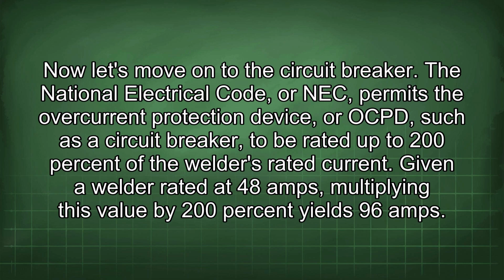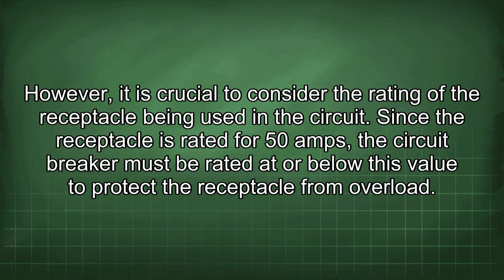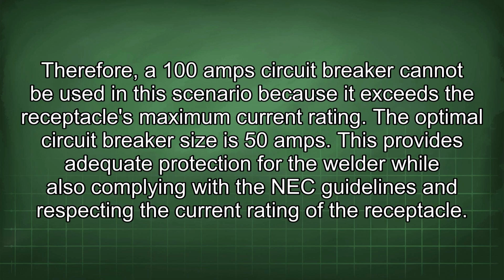The National Electrical Code, or NEC, permits the overcurrent protection device, or OCPD, such as a circuit breaker, to be rated up to 200% of the welder's rated current. Given a welder rated at 48 amps, multiplying this value by 200% yields 96 amps. However, it is crucial to consider the rating of the receptacle being used in the circuit. Since the receptacle is rated for 50 amps, the circuit breaker must be rated at or below this value to protect the receptacle from overload. Therefore, a 100 amp circuit breaker cannot be used in this scenario because it exceeds the receptacle's maximum current rating.